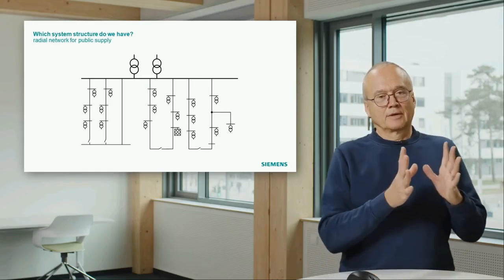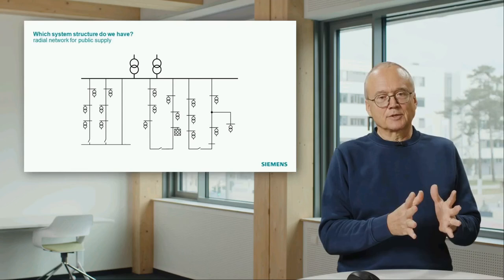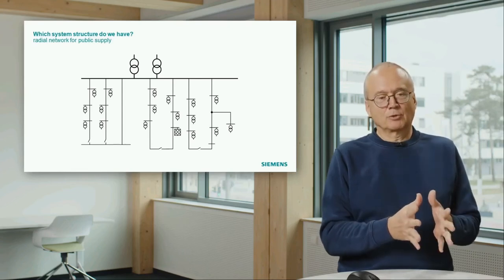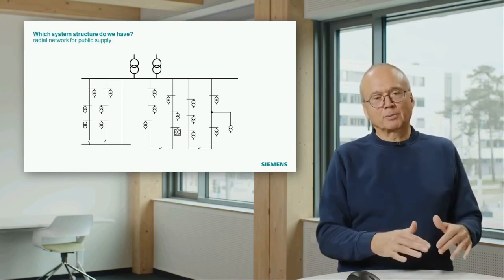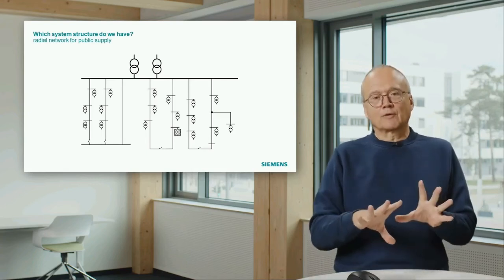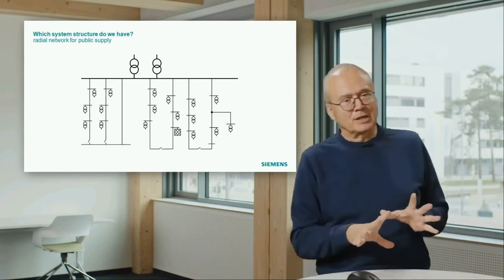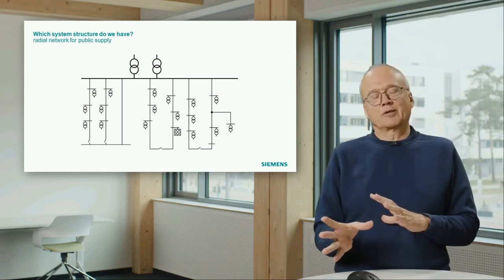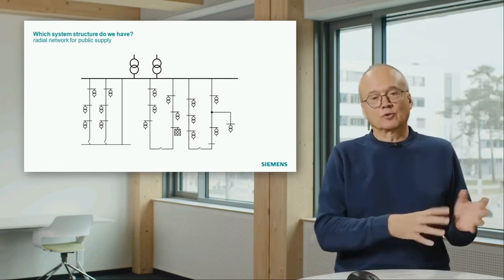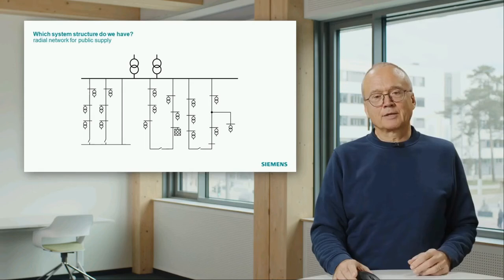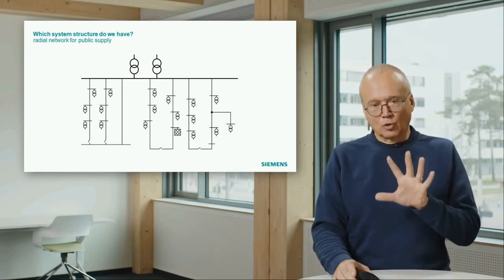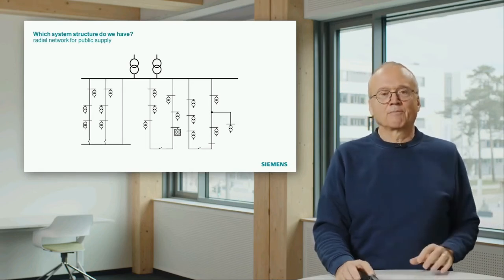That means normally you have a radial system, and we will see that's important for protection. After protection has worked, you can reconfigure the system. That will take some time, depending whether you have remote control or you have to drive there to reconnect that. The important point here is that normal operation is a radial system.